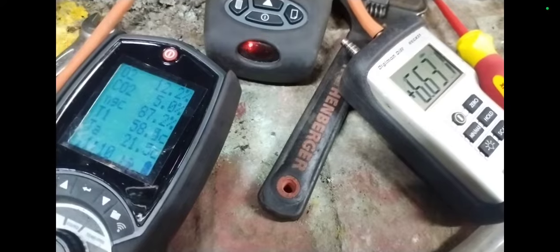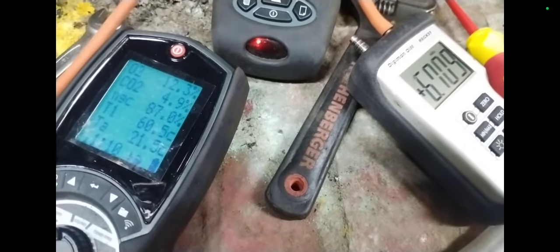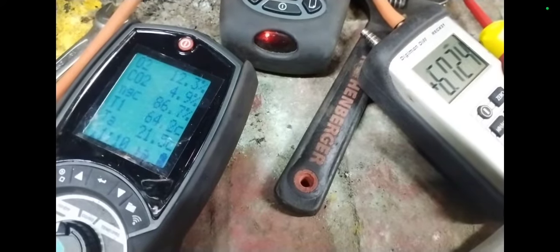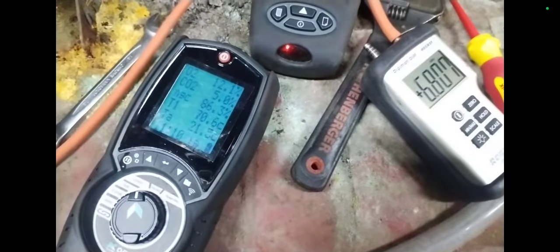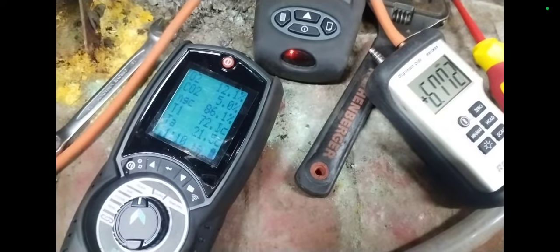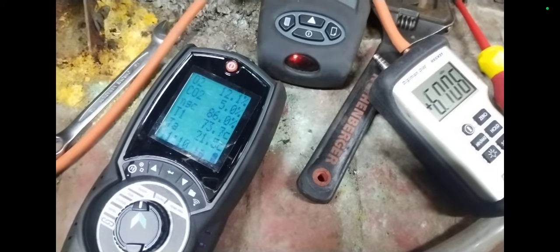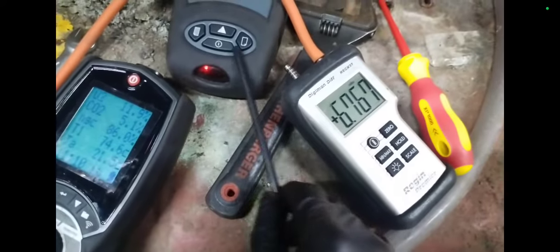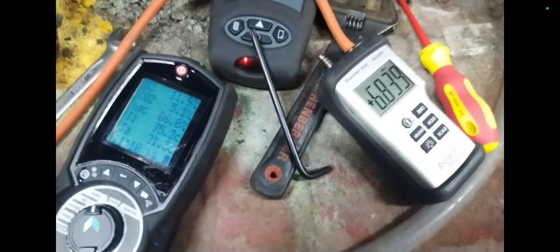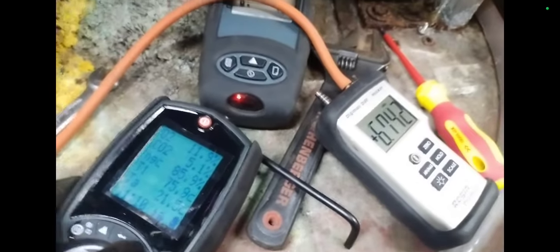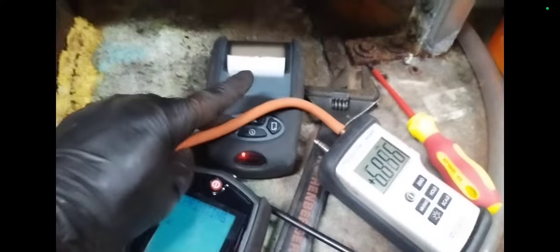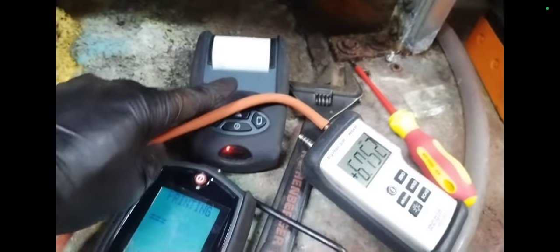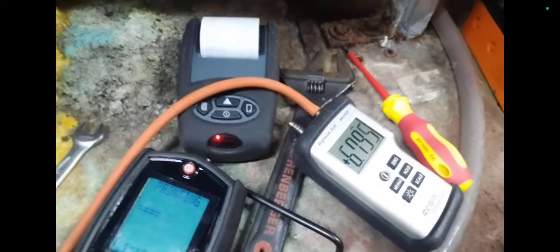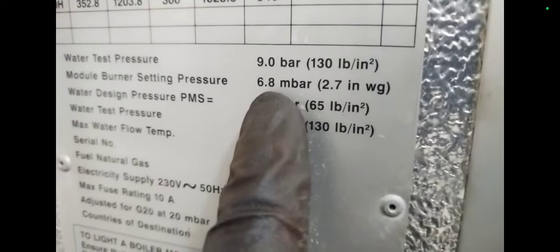This one I'm tweaking up to the 6.8. I think this bottom right one became the best of the 4 boilers in terms of smooth ignition. Yep, 6.8 burner pressure. And at the same time checking the combustion is good. I think the fixed spanners were the most helpful tool for me in this service. Without those fixed spanners, it'd be almost impossible to work on this unit, especially if you need to take it out and wash it down. Here we are, 6.8 millibar.